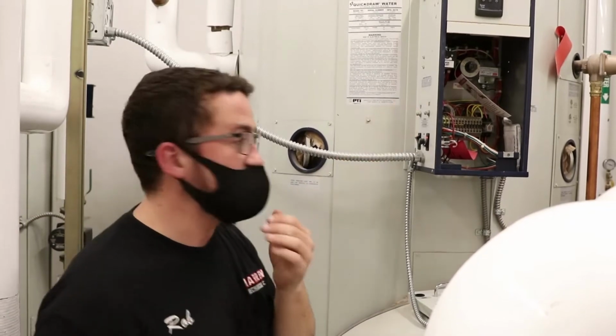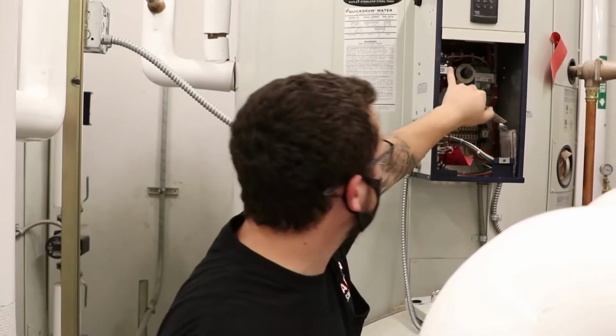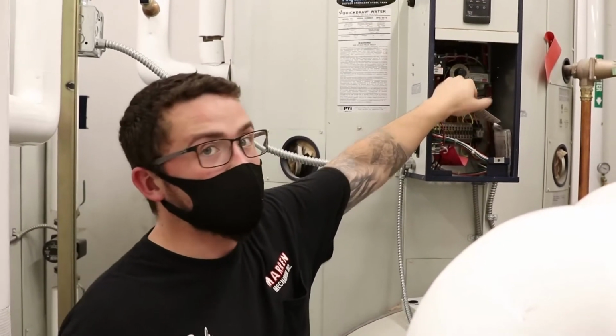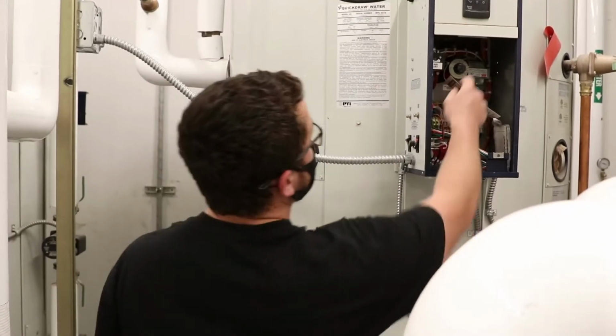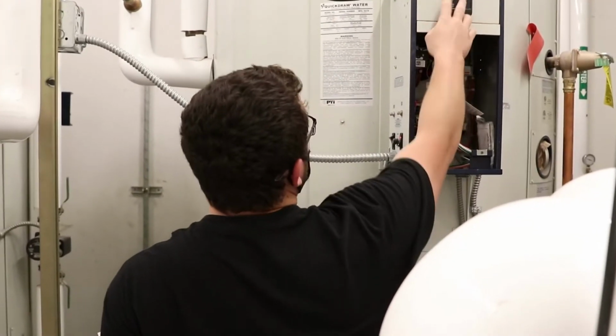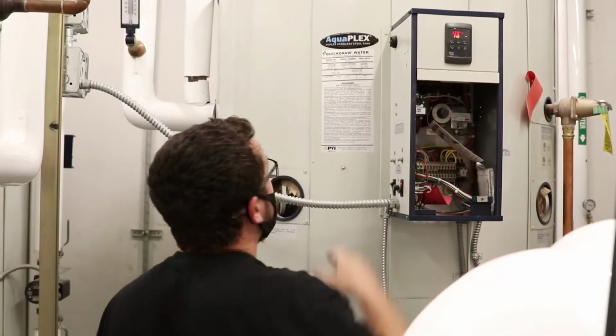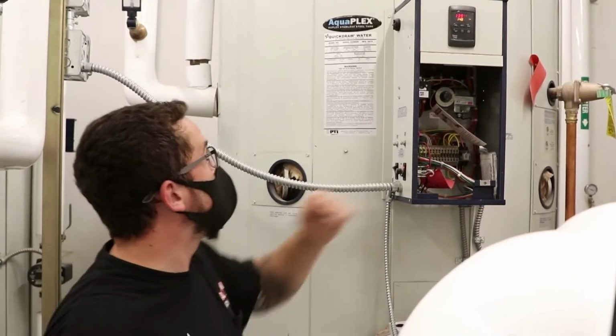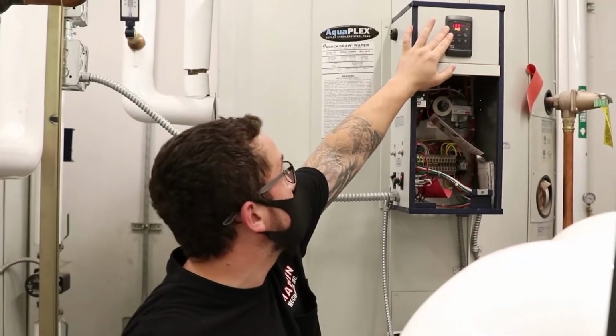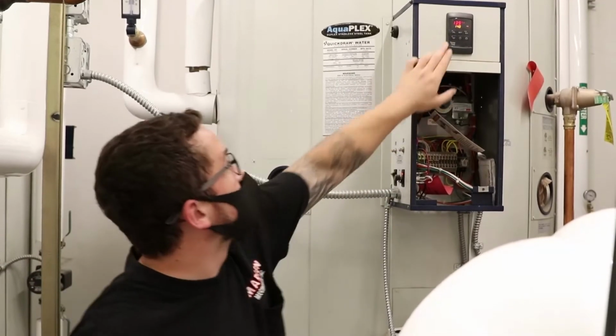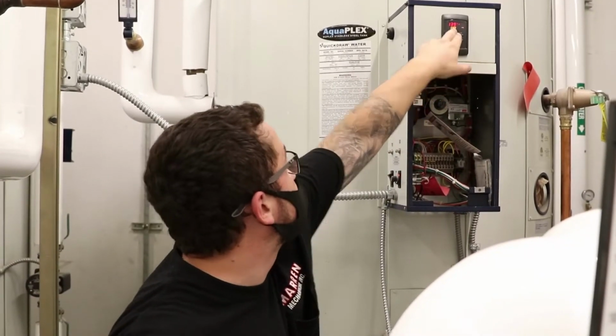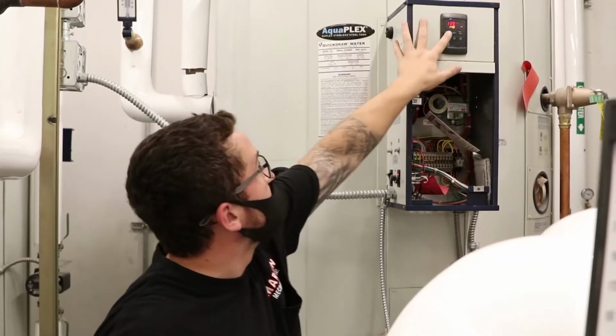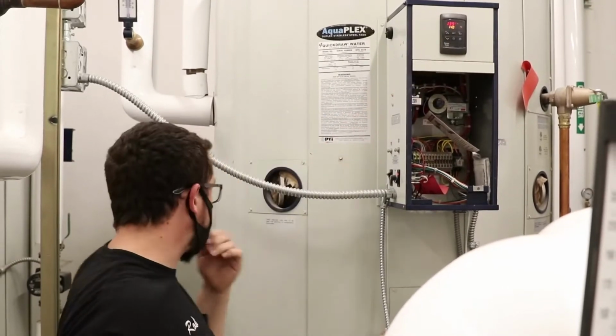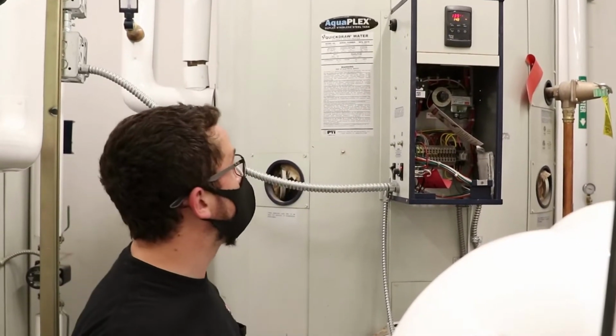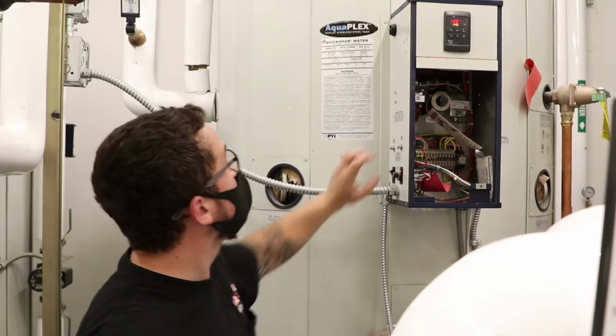That should be tested. In addition, this high limit control should be tested annually, and these controls should be tested for accuracy. You're also going to want to make sure that these temperature displays are accurate. This red number is coming off a sensor that's at the top of the tank. This yellow number is coming off a sensor that's at the middle of the tank. It's just telling you the temperature at two different points in the tank.